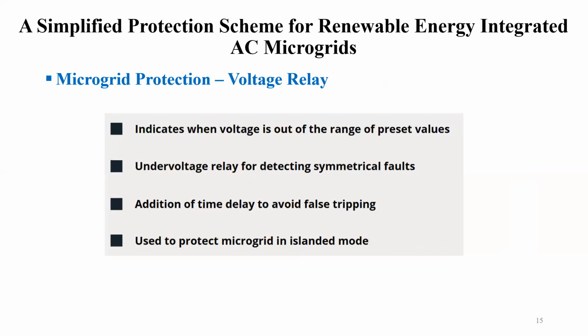Then we have the voltage relay, and that is used when the voltage is out of range of the preset values, or it's over or under the allowed limit. So the undervoltage relay is used for detecting symmetrical faults, with the addition of a time delay to avoid false tripping, and it is used to protect the microgrid in the islanded mode of operation.